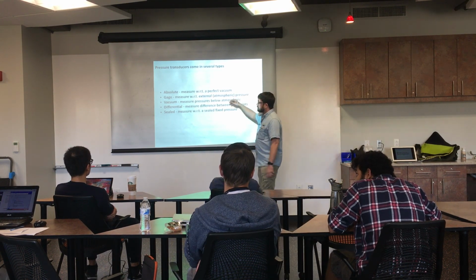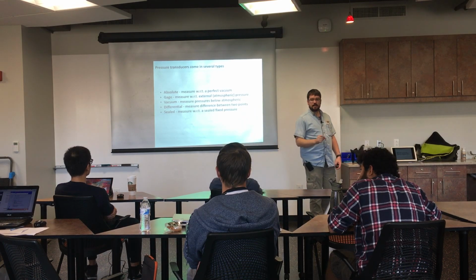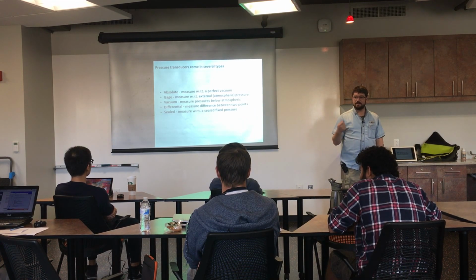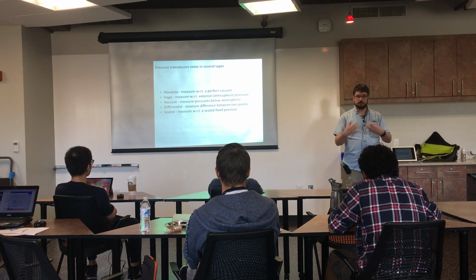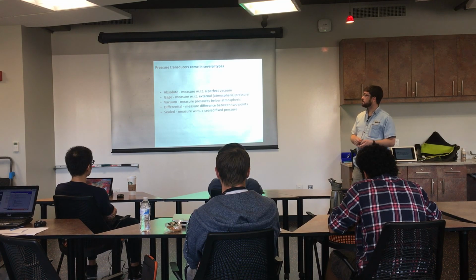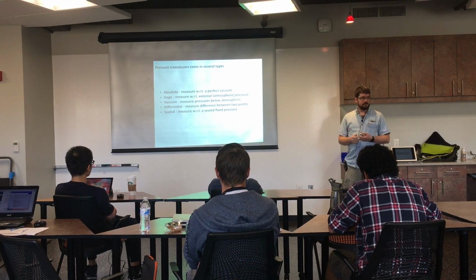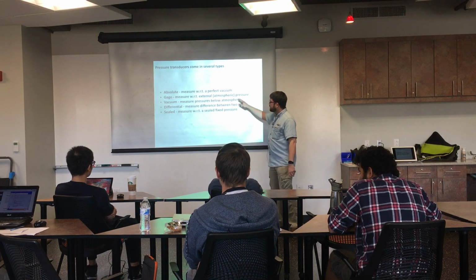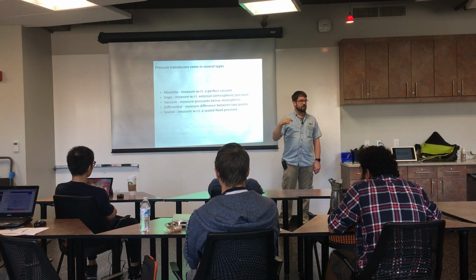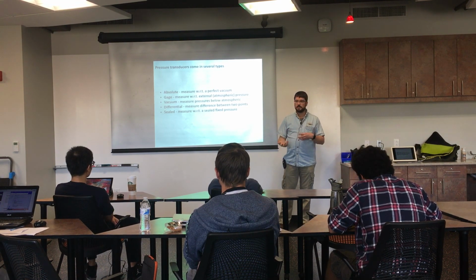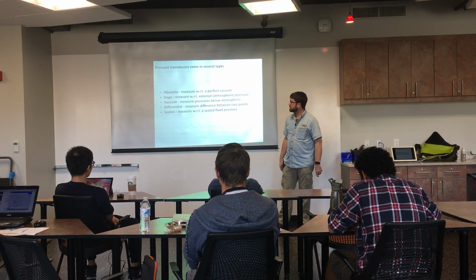The gauge pressure, which is what we deal with a lot of the time, is relative to atmosphere. So if we had a gauge pressure transducer, right now it would say 0, unless you blew on it or something to increase the pressure inside. So it's relative to the current atmospheric pressure, which can change over time as storms come through and all that. So they're vented, basically. Vacuum transducers are used to measure below atmospheric pressures. It's not common, though it does exist, to have a transducer that can do vacuum and above atmospheric pressure in one transducer. They're generally designed for one or the other, and doing the opposite can damage it.